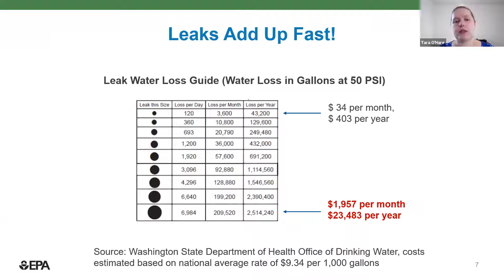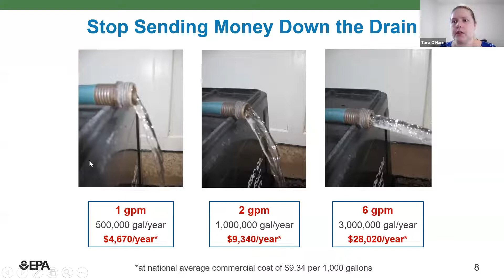To give you some other perspective, here's what actual water usage looks like. We're all familiar with a garden hose. On the left is a low flow, about 1 gallon per minute, which can add up to almost $5,000 a year in costs. On the right is a garden hose at full flow, like in a single pass cooling situation, which can add up to about $28,000 per year. That's really significant, and you don't necessarily need to pay it.